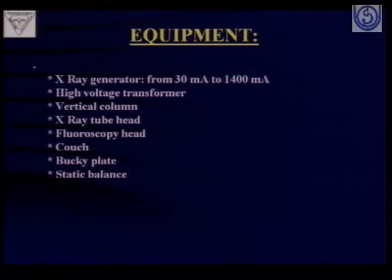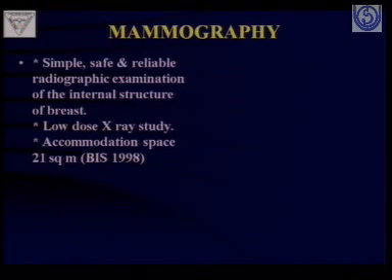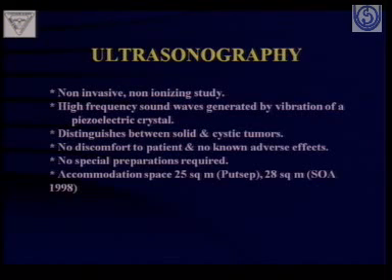Various types of equipment are there in the X-ray department, as we were discussing earlier, and as Professor Arora also brought out. The imaging requirement is that you have mammography equipment nowadays, which is a simple, safe and reliable radiographic examination for the breast. It is a low dose X-ray study, and the accommodation requirement is approximately 21 square meters.